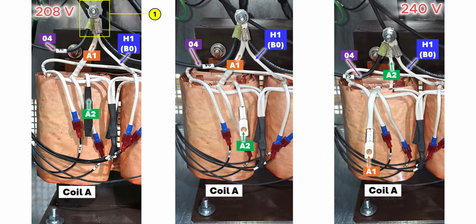Number 1, remove the shrink wrap covering the H1 tap connections. Number 2, remove the shrink wrap covering wire A2. Number 3, keeping H1 connected to wire 04 from the AC circuit breaker, pull wire A1 out. Number 4, place wire A2 together with wires H1 and 04. Tighten the lugs for these wires together. Later, we'll shrink wrap the wires connected at H1 and separately wrap the unused wire A1.